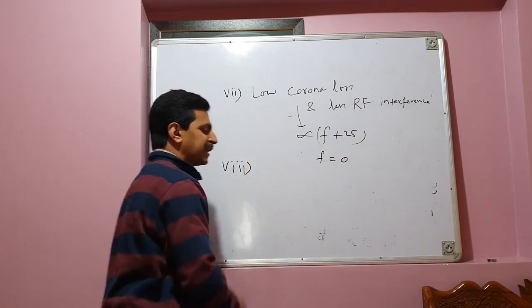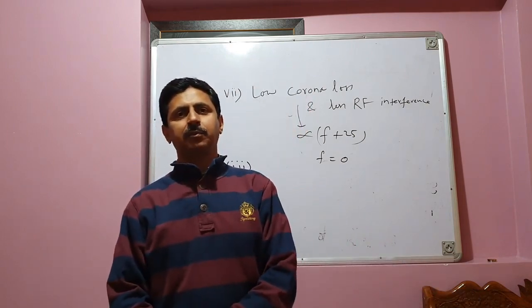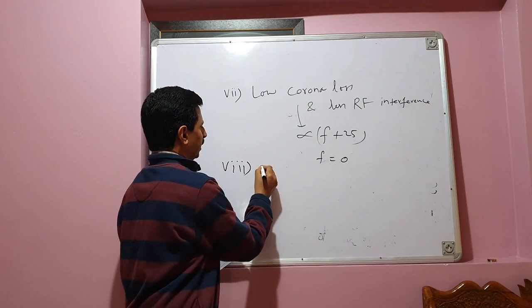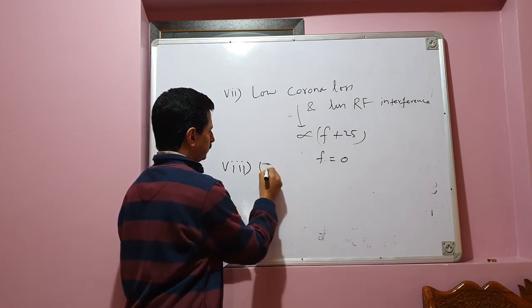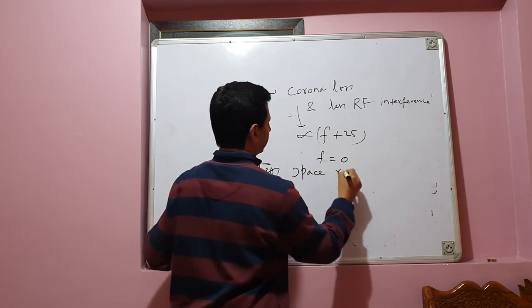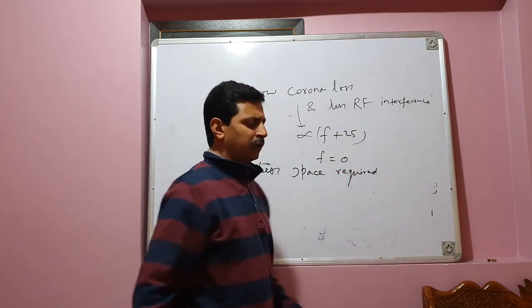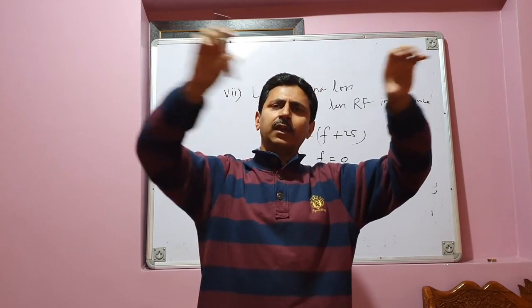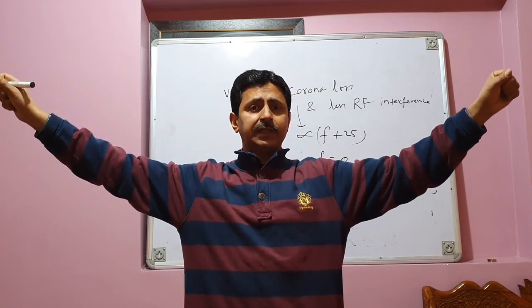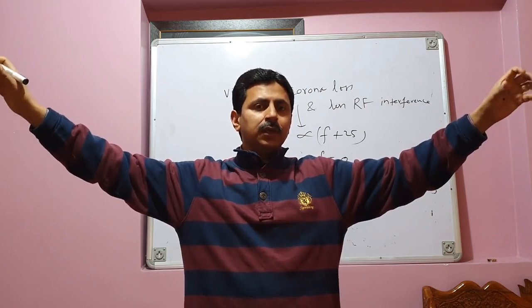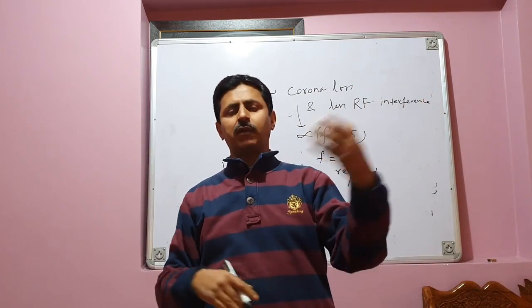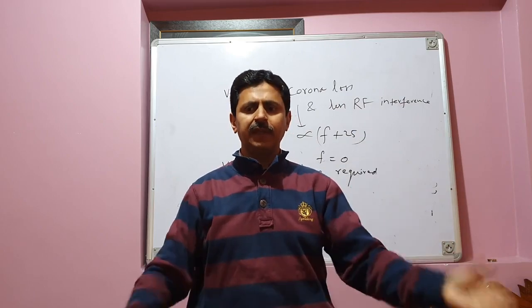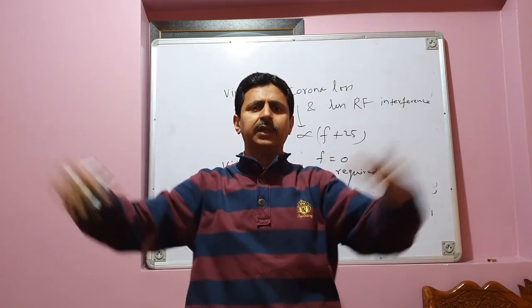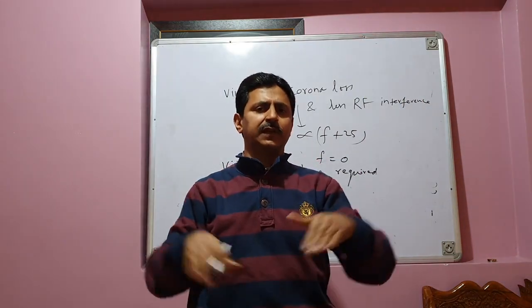Okay, so this is the next advantage. What is the next advantage of HVDC power transmission over AC power transmission? Next is simpler, less space required. This is very important. When you are transmitting power over an AC transmission line or over a DC transmission line, you need very long transmission lines, and those transmission lines are supported on transmission towers. Those are very big transmission towers, each tower costing lakhs of rupees. Very high, very broad transmission towers, and then there are strings of insulators, and on those insulators you support your transmission lines.